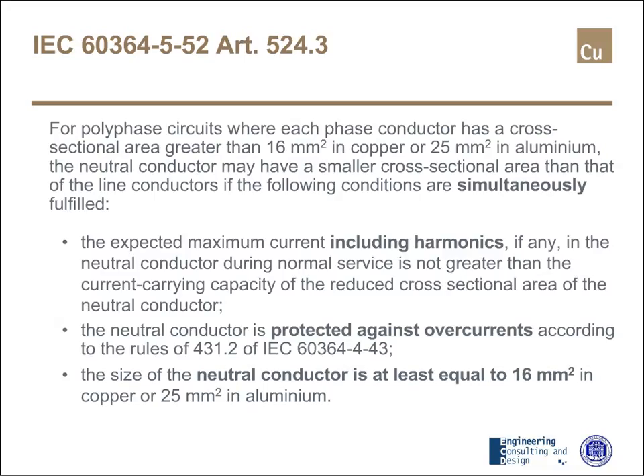The first one: the expected maximum current including harmonics, and this is the main issue for today, if any, in the neutral conductor during normal service is not greater than the current carrying capacity of the reduced cross-sectional area of the neutral conductor. I have to consider the real current flowing into the neutral and not just the theoretical current. Considering this current, obviously, I have to consider also the effect of harmonics.